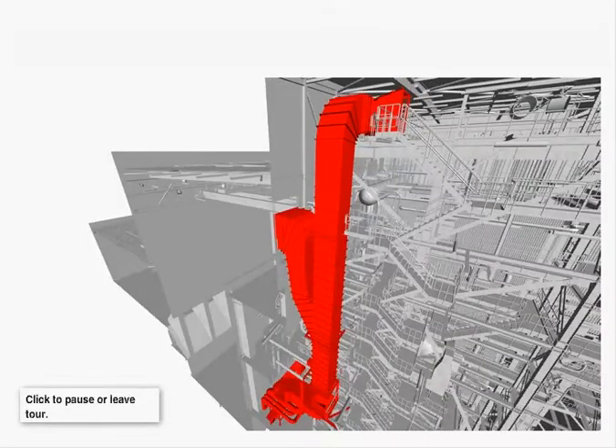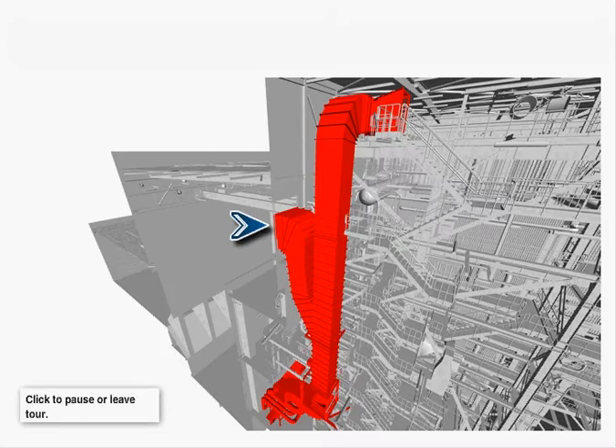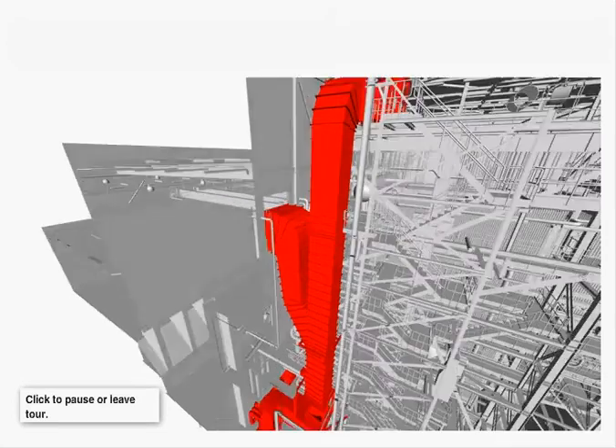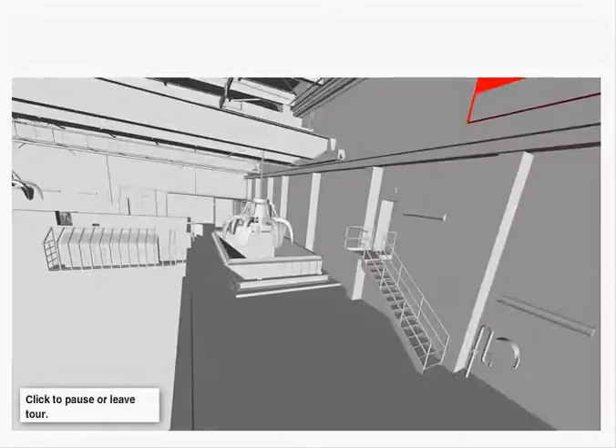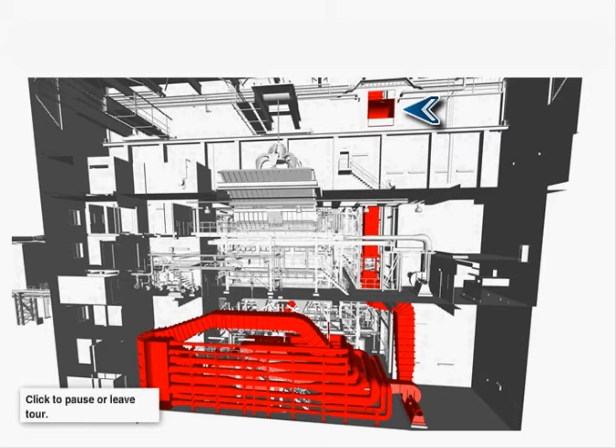The combustion air is divided into primary and secondary air. The primary air goes to the combustion grate and the secondary air goes to the furnace and the boiler. The primary air is taken from the bunker area and the top of the boiler building. The combustion air intake ensures a constant low pressure in the bunker area. The air that's drawn into the building is fed through the furnace where it's combusted, destroying odors. This means that there's no odor from the waste and therefore no smell in the neighborhood.